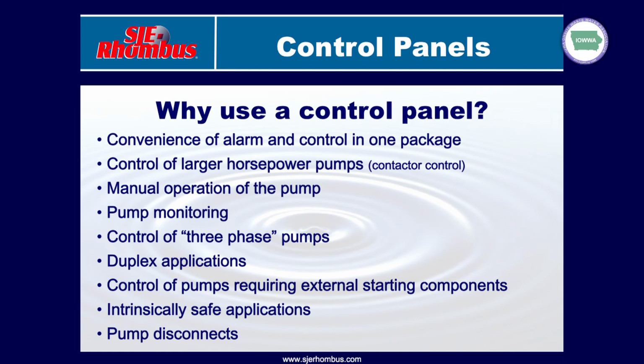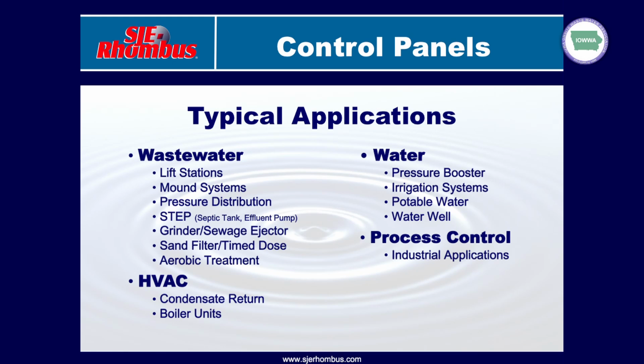And then with a control panel, we also have the ability to incorporate pump disconnects into the panel. So it just gives you a nice safe way of interrupting power to the pump. If you have to do any service work, you can incorporate either circuit breakers or rotary style disconnects into the panel. Allows us to kill power to the pumps. There's a few of the different applications where we see and manufacture control panels for. The vast majority of our business, probably 90% or better, is in the wastewater industry. Though we're seeing more and more on the clean water side of the fence with constant pressure systems.